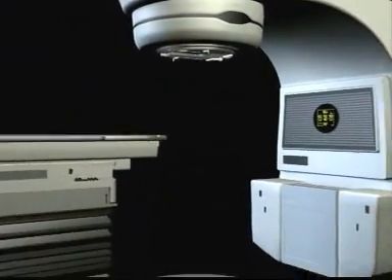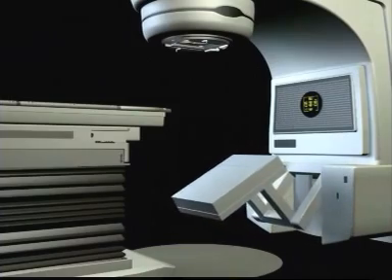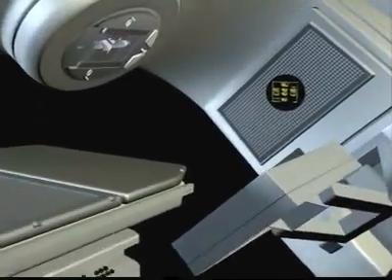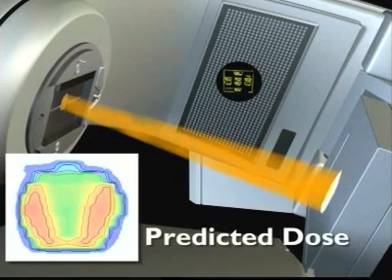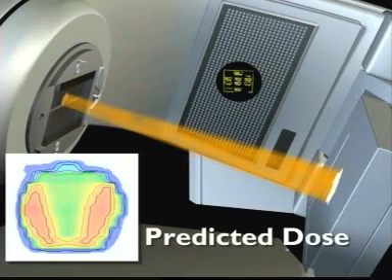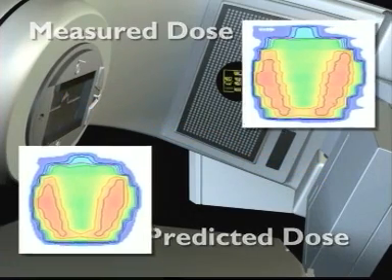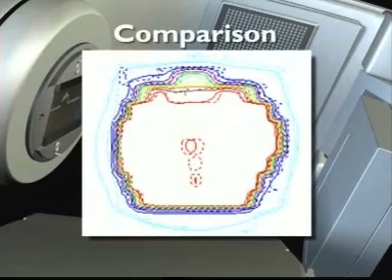IMRT treatment delivery is verified using Varian's portal vision system mounted on a robotic arm. The IMRT field is delivered without the patient. The predicted dose from the Eclipse Helios Treatment Planning System is compared with the measured dose from portal vision. Different tools permit the analysis and comparison of the two dose matrices.